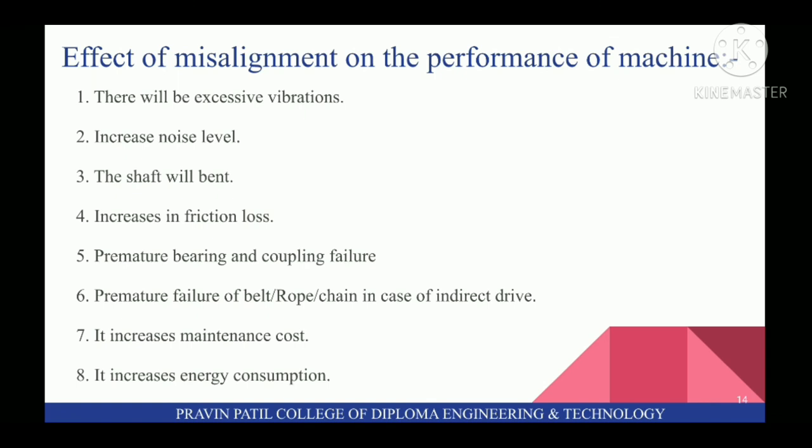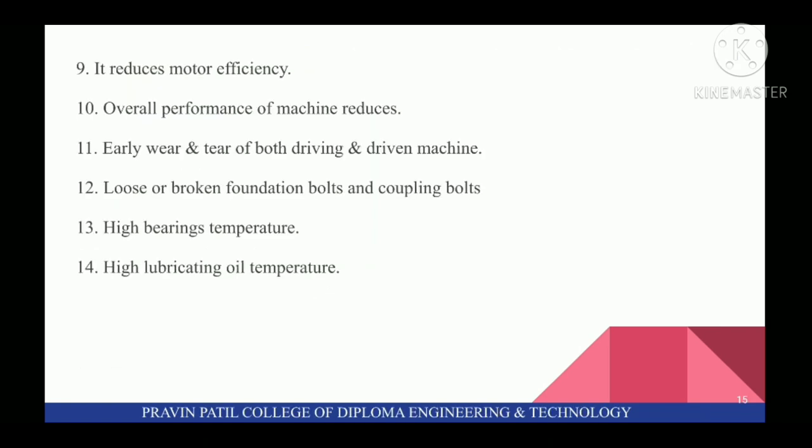Next topic is effect of misalignment on the performance of machine. First, there will be excessive vibrations. Second, increased noise level. Third, the shaft will bend. Fourth effect is increasing friction loss. Fifth is premature bearing and coupling failure. Sixth is premature failure of belt, rope, chain in case of indirect drive. Seventh, it increases maintenance cost. Eighth, it increases energy consumption. Next effect, it reduces motor efficiency. Tenth, overall performance of machine reduces.